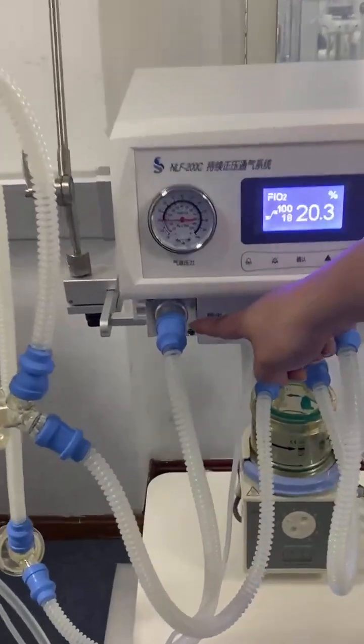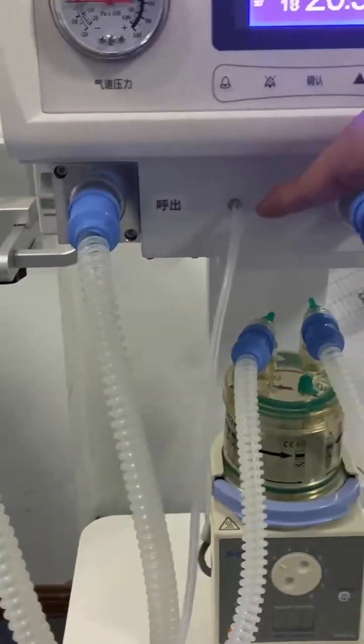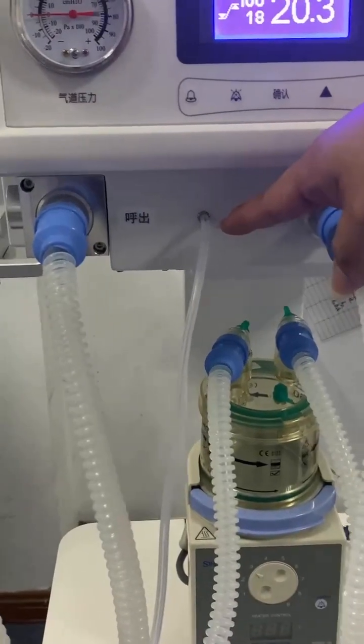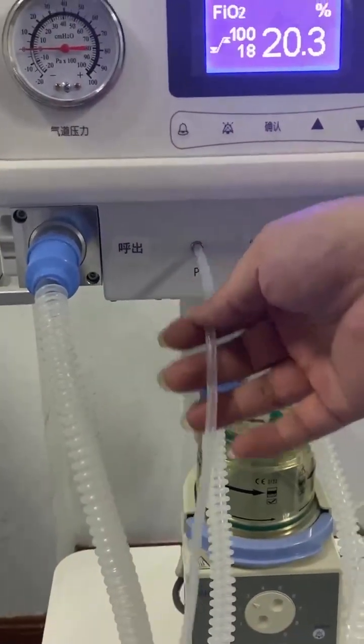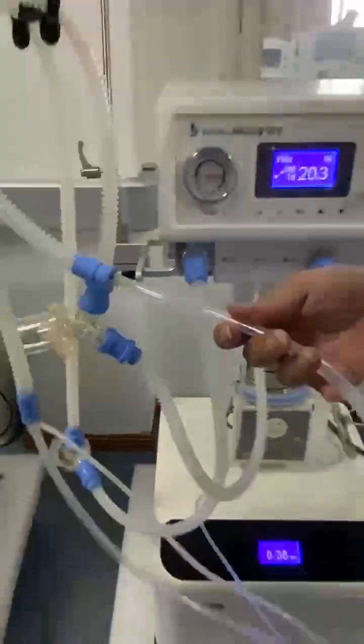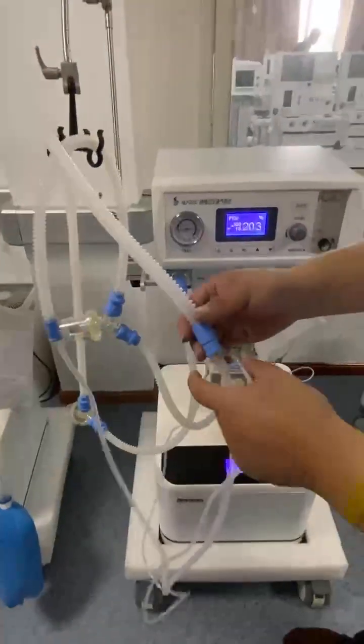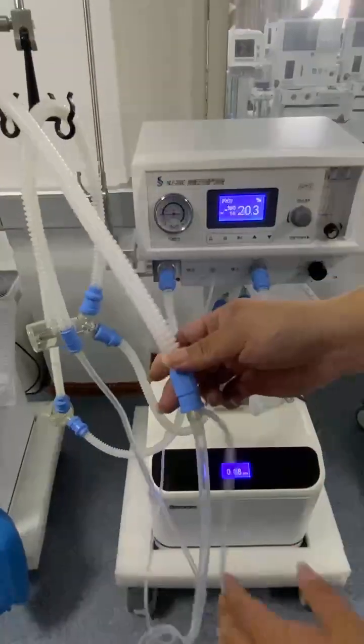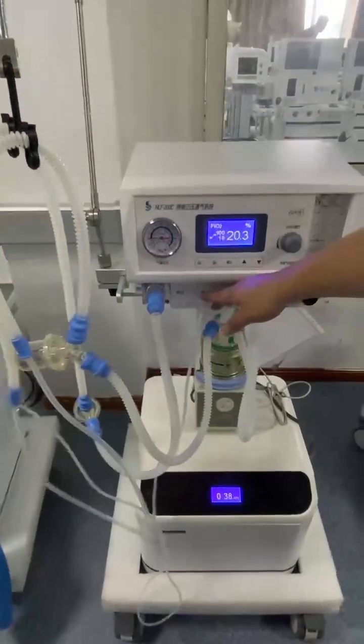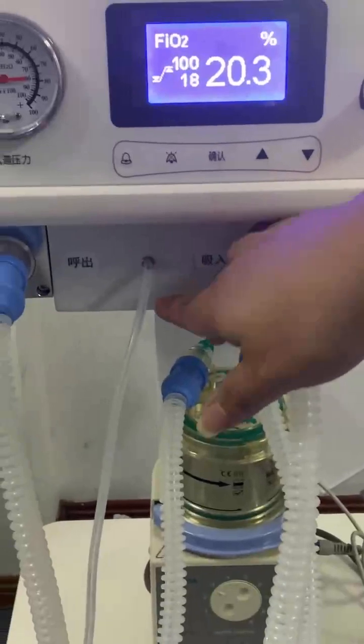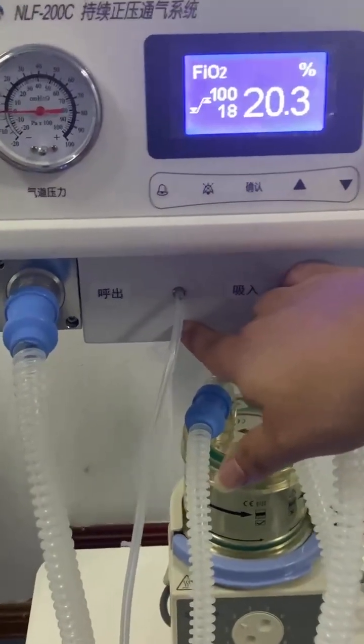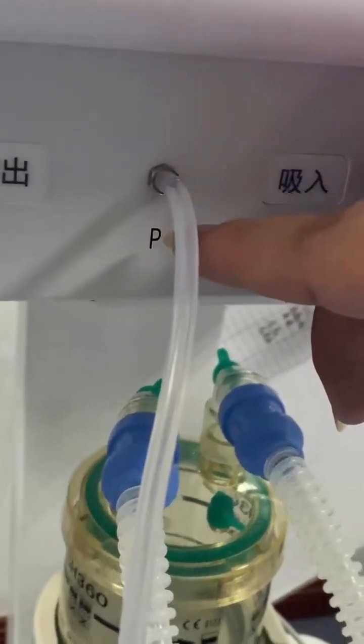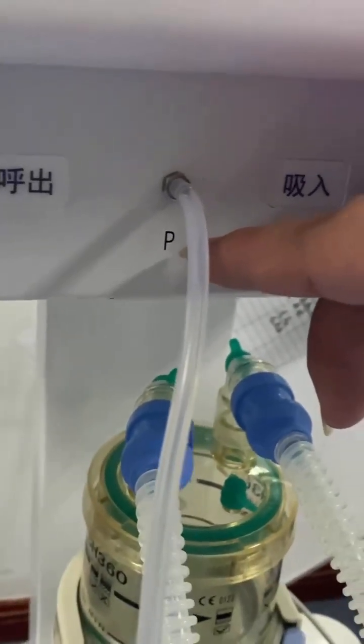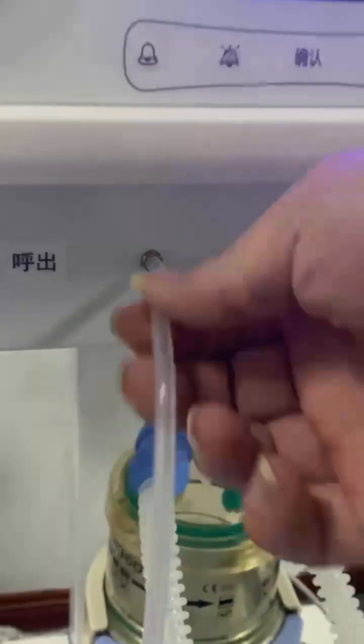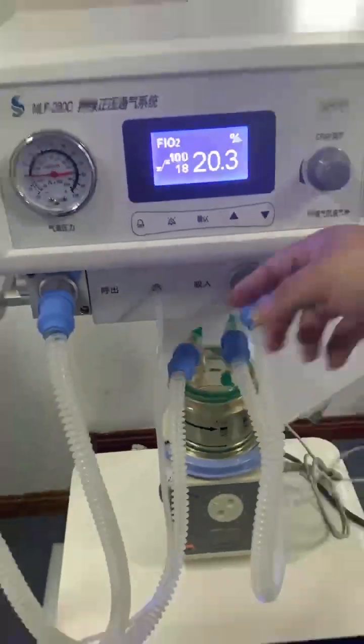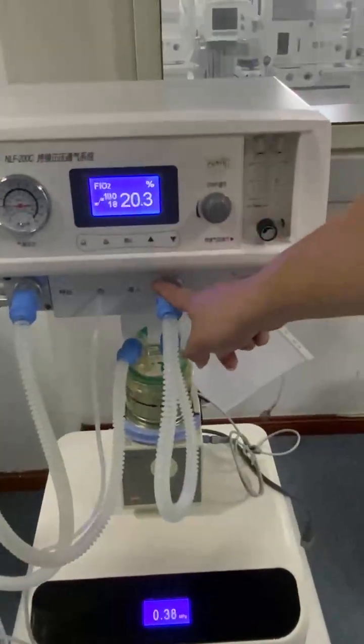This port will be the expiration port, and here, this one is also very important. We must ensure this pipeline is connected very well, and you should see another side. We must connect by this port. This pipeline is very important because this one is the pressure sampling line. Actually here it's showing a symbol P, it means the pressure. So if we want to use the machine properly and we want to test and monitor the pressure from the patient end, we must connect the pressure sampling line. And this port is the inspiration port.